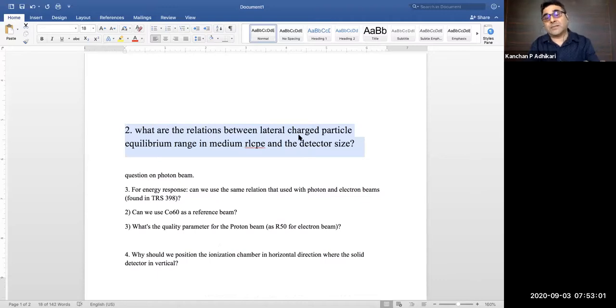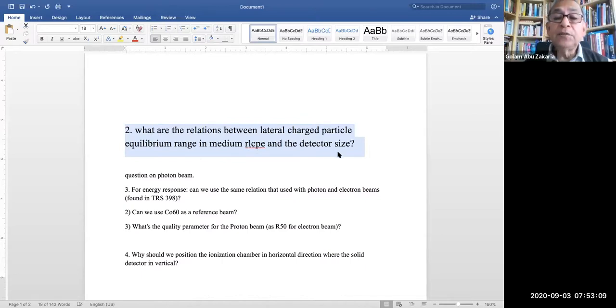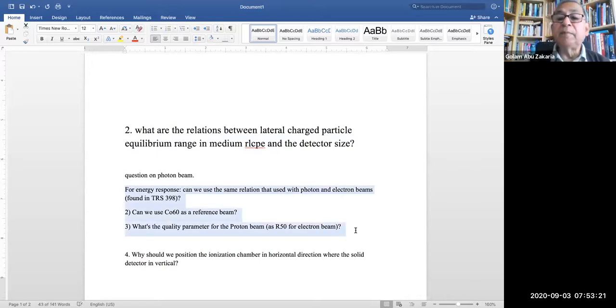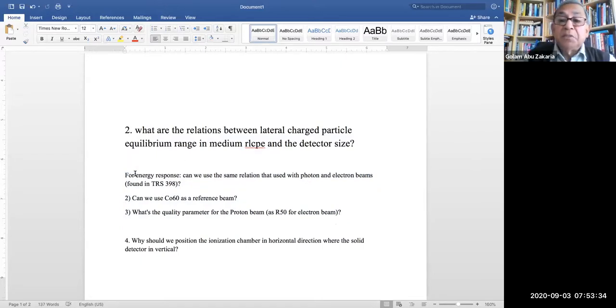What are the relations between the lateral charged particle equilibrium range in the medium, RLCPE, and the detector size? Yes, I have given a formula. The minimum field is 2 times RLCPE plus D. That means when you have a detector, maybe 0.5 centimeter diameter, and you have selected an energy, maybe 15 MeV, then 2 centimeter, and the field must be 2.5 centimeter larger than that. So there is a relation. You can calculate it.